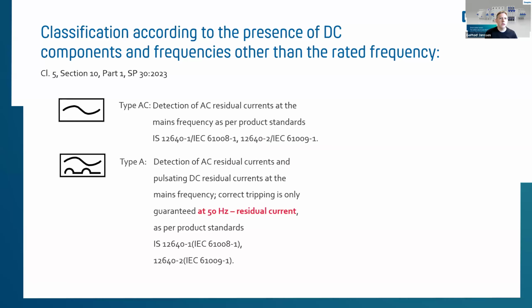But the AC type is very limited. It's only to detect AC residual currents. And in today's world, where we have completely different loads, not the standard loads from the past, the AC type is not the best selection anymore. So to have higher protection, at least the type A should be used. The type A as well is able to detect AC residual currents, but additionally, pulsating DC currents at the mains frequency 50 cycles.